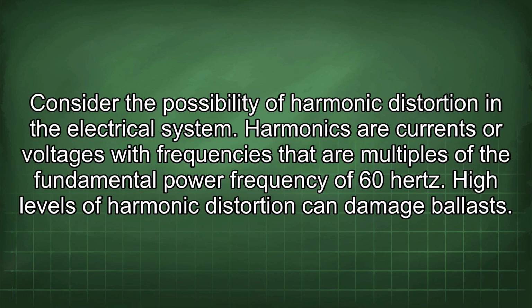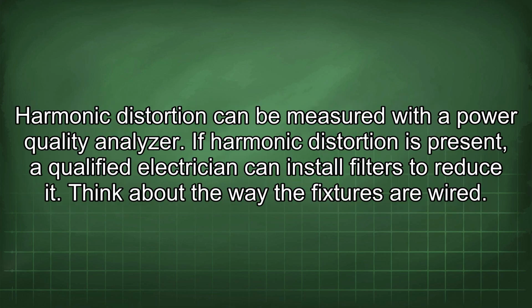Consider the possibility of harmonic distortion in the electrical system. Harmonics are currents or voltages with frequencies that are multiples of the fundamental power frequency of 60 Hz. High levels of harmonic distortion can damage ballasts. Harmonic distortion can be measured with a power quality analyzer. If harmonic distortion is present, a qualified electrician can install filters to reduce it.